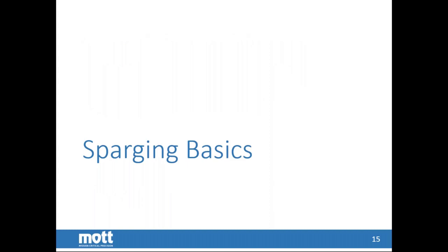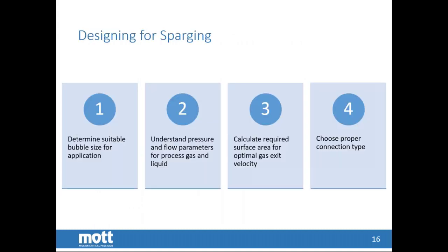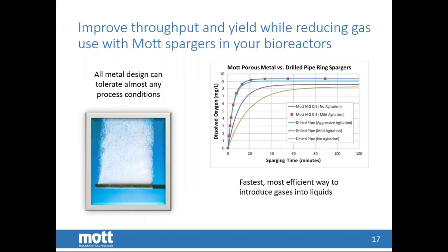We'll shift gears a little bit here and go into sparging basics. Designing a sparger, we will ask quite a few questions trying to determine the best media grade for your application. We need to understand the flow and pressures of the process. With that information, we can then calculate the surface area required to get the gas exit velocity we're looking for. And part of the conversation with customers is determining the proper connections for the gas, as well as for either the tank or the inline application. Using a porous metal for the sparger, you can see the image on the left, you get a lot of tiny bubbles. And if you compare it to a drill pipe, where you get fewer but much larger bubbles, the drill pipe has a lot lower surface contact area of the gas to the liquid.